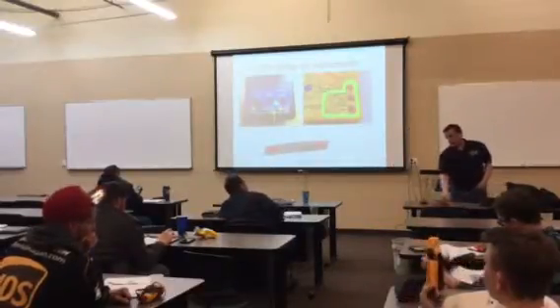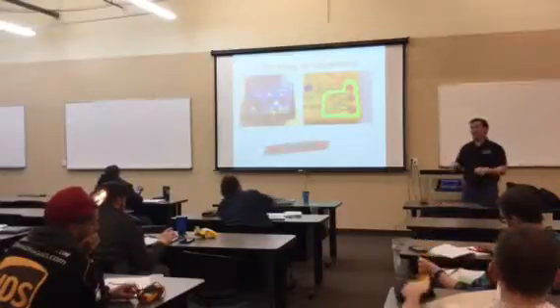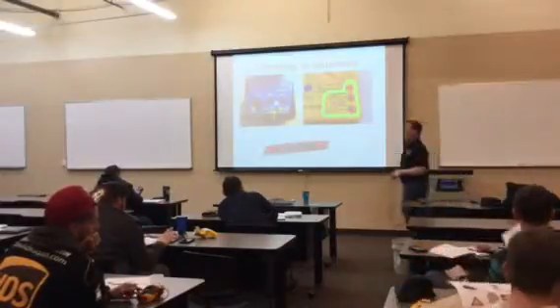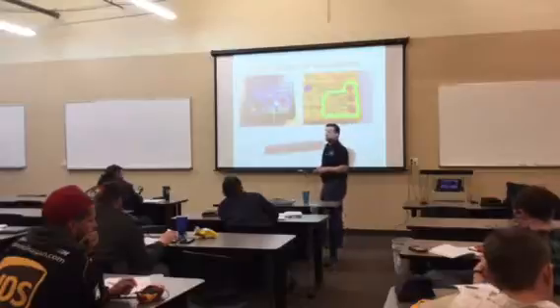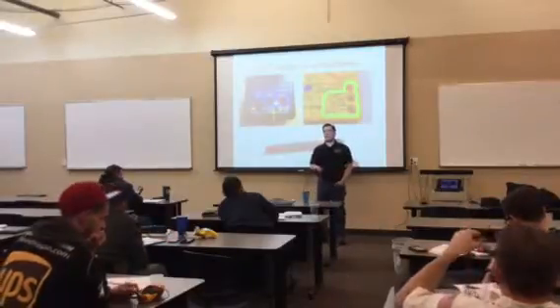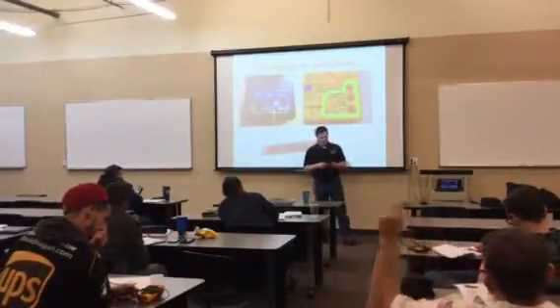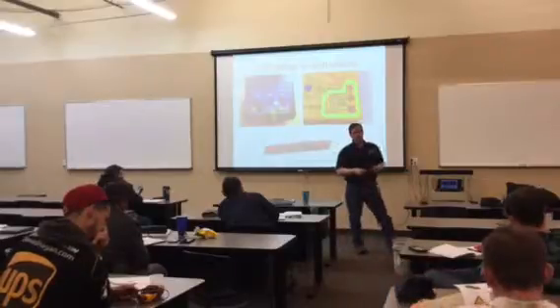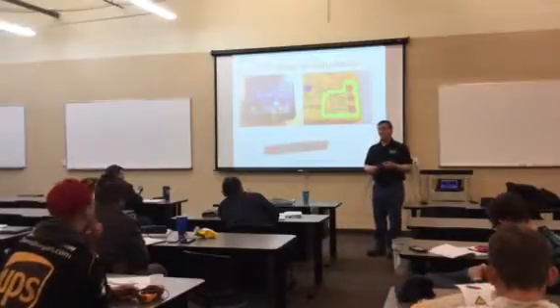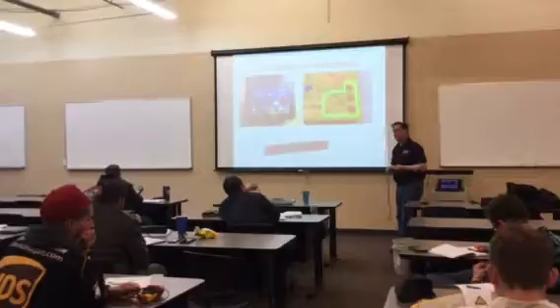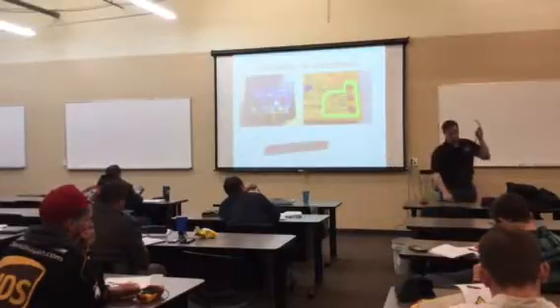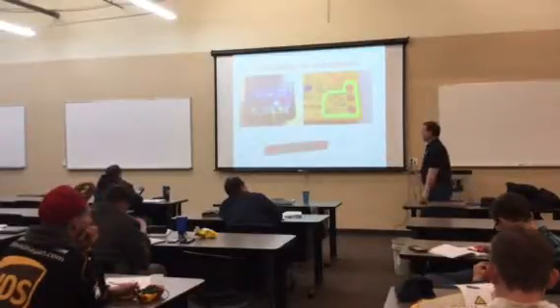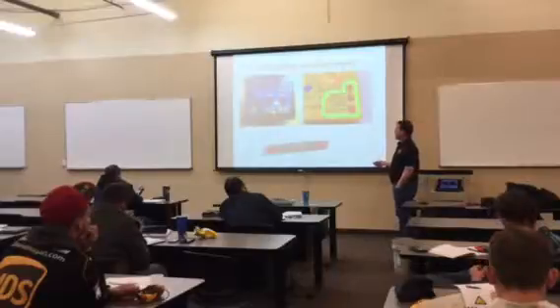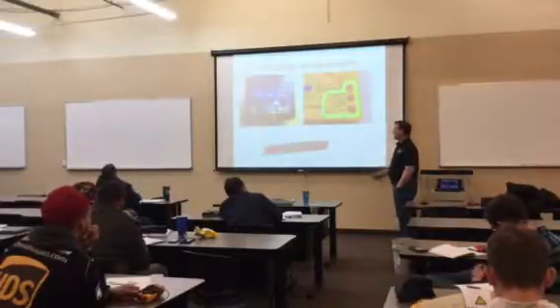Your test leads also have Cat ratings on them, so when you're buying replacement test leads, pay attention to the Cat rating. Cheaper is not better when it comes to test leads. Everything that plugs into your meter should have a CAT rating on it somewhere. This one here is also 1,000 volts at Cat 3 and 600 volts at Cat 4, 1,000 volts at Cat 2.